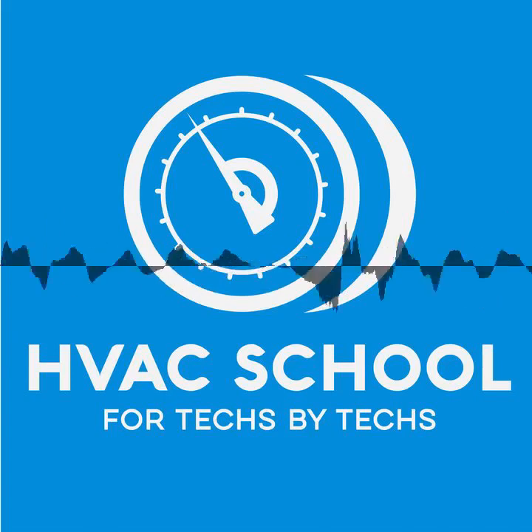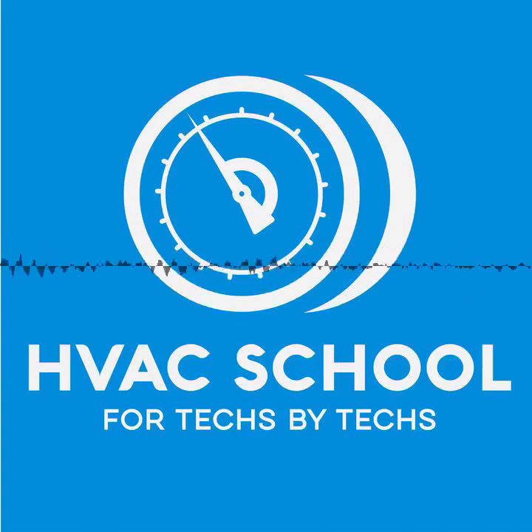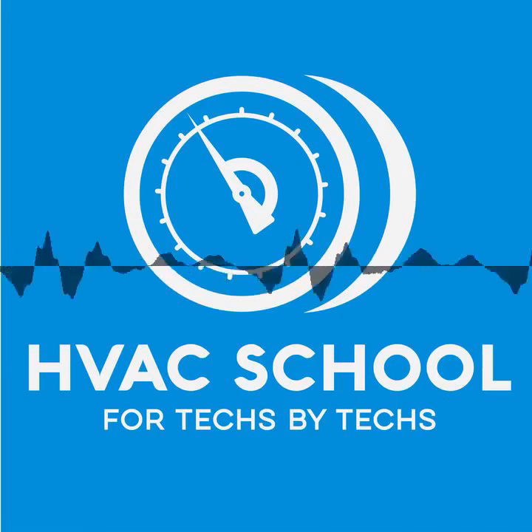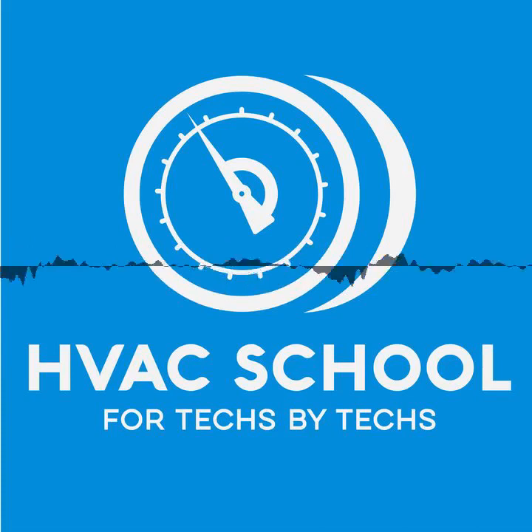happened with Copeland and the rust inhibitor in the compressors that was causing issues with expansion valves. A lot of manufacturers came out and actually gave part numbers for high-performance lubricants to put in the system. And Carrier did this, and I think some others did as well, in order to help combat this problem with the rust inhibitor. And clearly, rust inhibitor in and of itself is also an additive. So there are already additives being put into systems in many cases by the manufacturer.